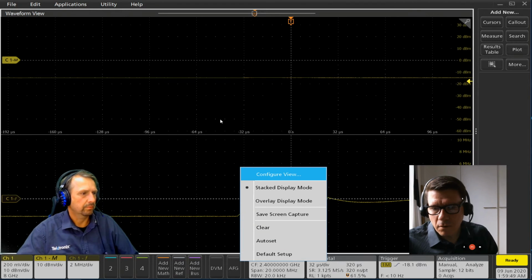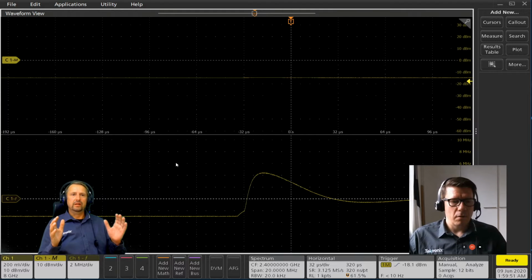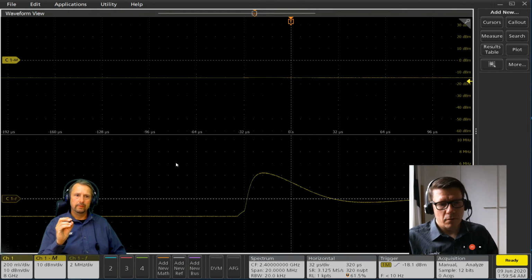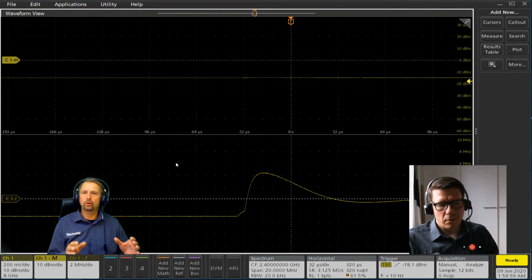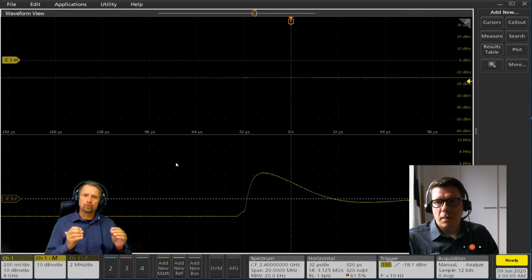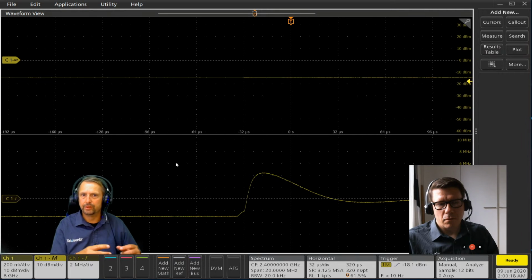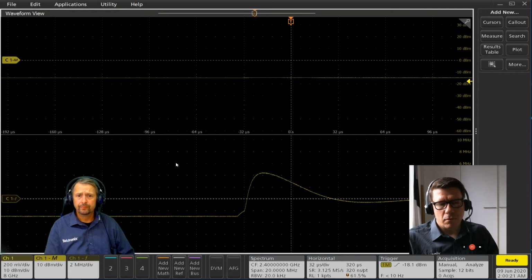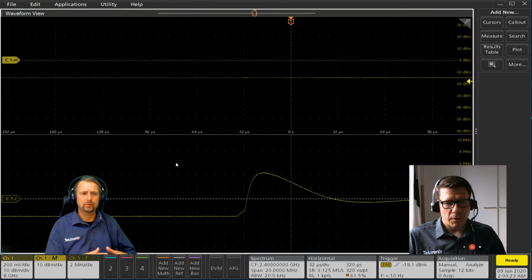Anyway. Any more questions before we go into this? What I'm saying is that the spectrum view concept allows you to focus on a frequency of interest. So can you do that only on one channel? You can do that on several channels. So there's one spectrum view behind each channel. What they do share, as I showed you prior, is the same sample rate, because this is how it works.